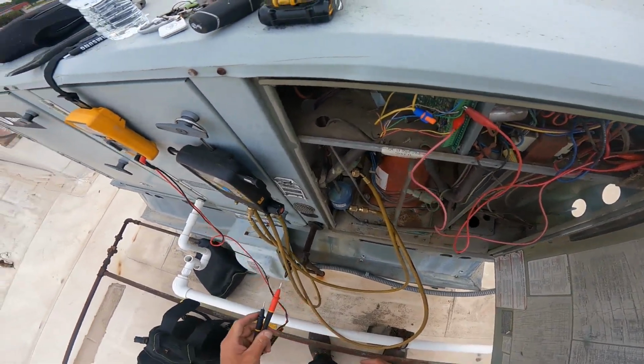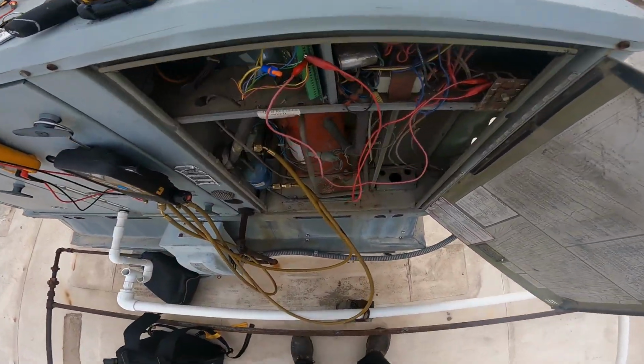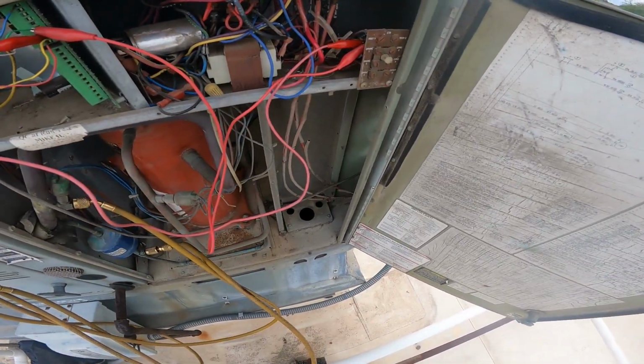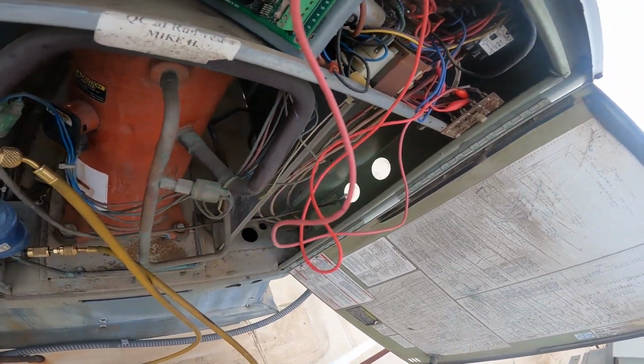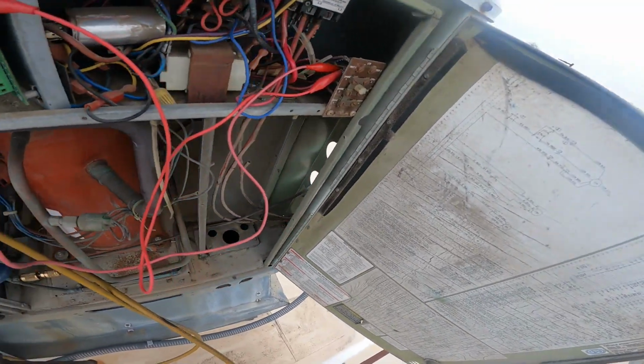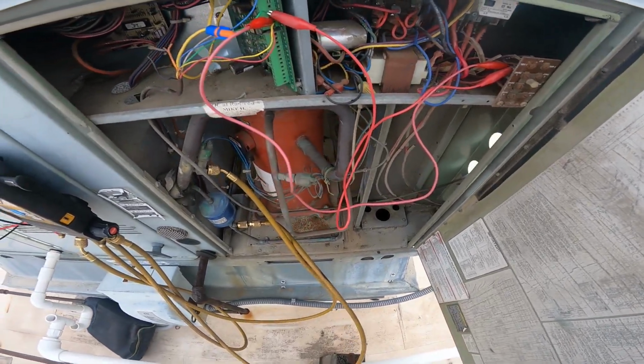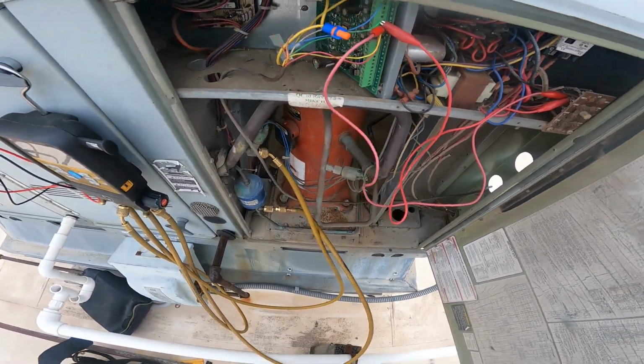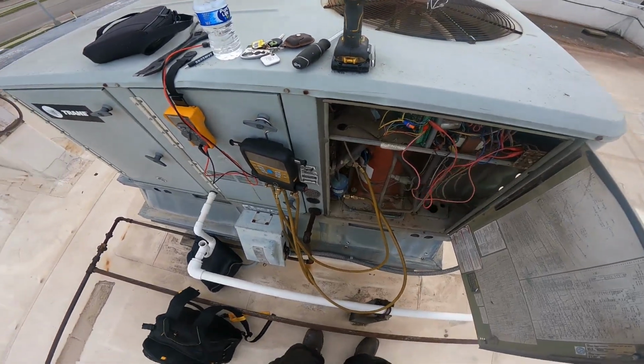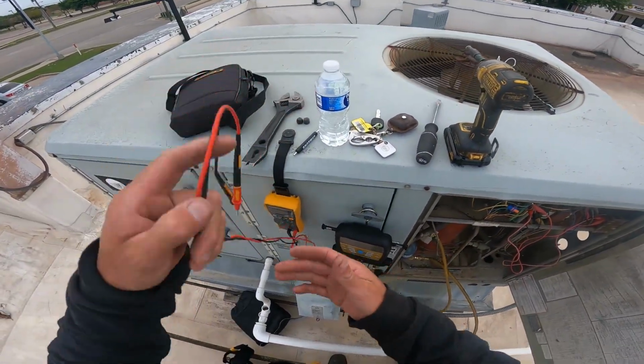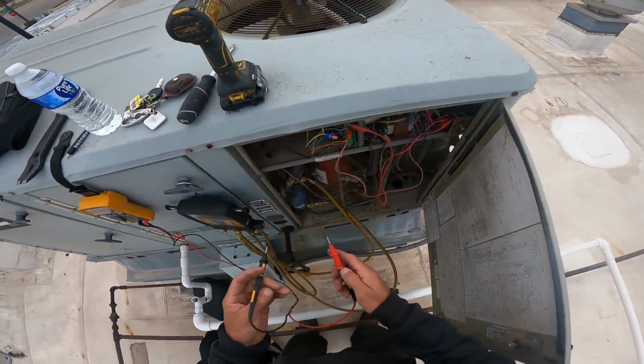Yes, okay, so I know the Y is getting voltage. Now the contactor's not pulling in. There's no way my leads are reaching the coil voltage on the contactor, so there's no way I'll be able to tell if it's pulling in. Ah, this is my coil voltage, so I can just check right there. See what we got.